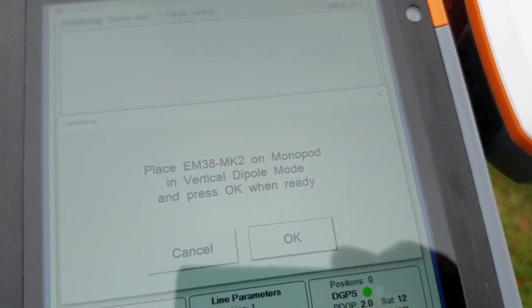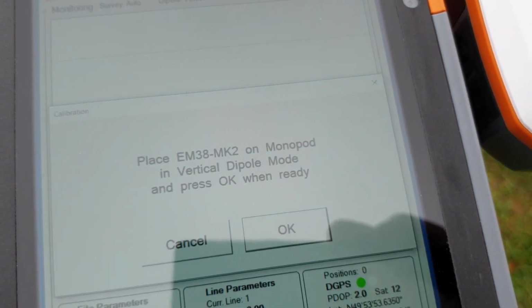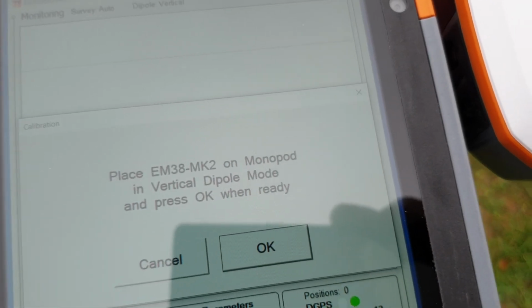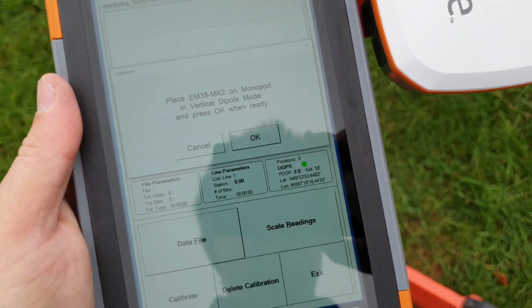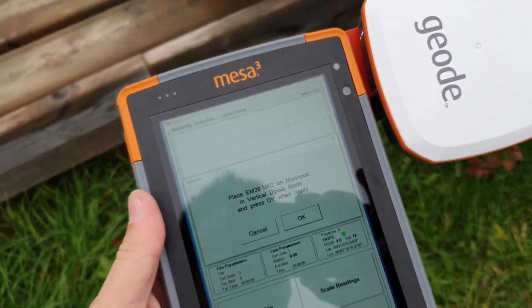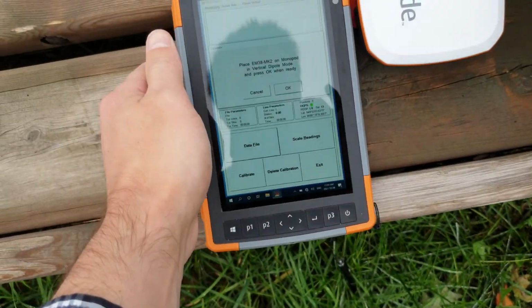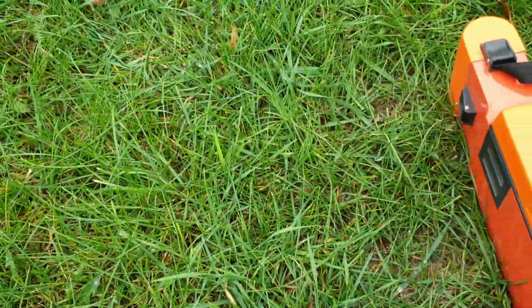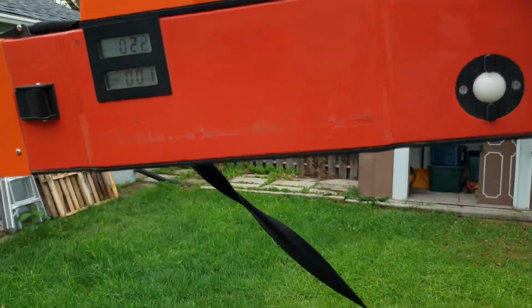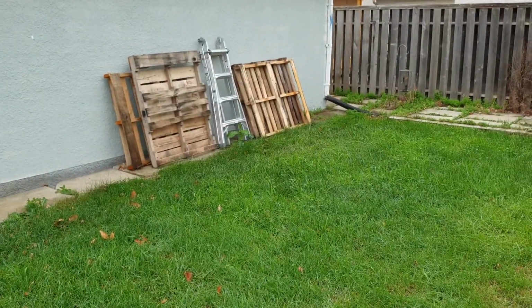All right, so now normally when you choose create calibration, I'm going to have to put this data logger down so that I have the other hand available. It will ask you to put it on the monopod in vertical orientation mode. So it's hard to see here, but this is suspended up in the air by about 1 meter, maybe 2.